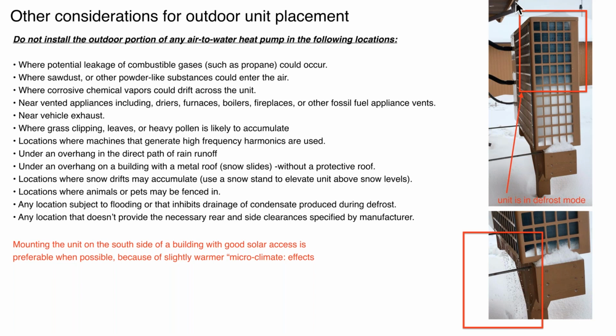I can imagine a situation where we have a 2-story house with a steep metal roof, and the snow might slide off of that metal roof and come down 2 stories and land directly on top of that heat pump. Obviously, that's not a good idea. So, when you're looking at a potential location for that heat pump, make sure you look at things like roof runoff or snowfalls or drifting snow. We want to keep it away from animals. We don't need the dog scratching on the side of the coil there, so to speak. Obviously, any kind of flooding, any kind of debris accumulation.